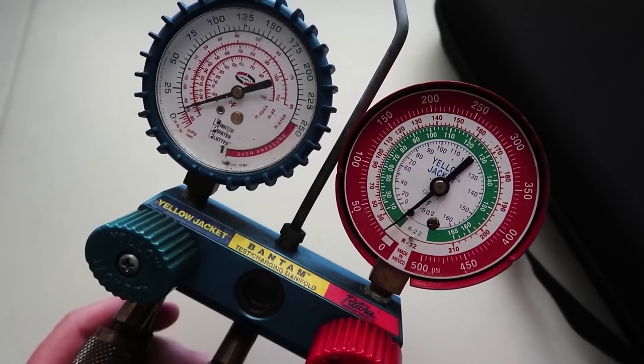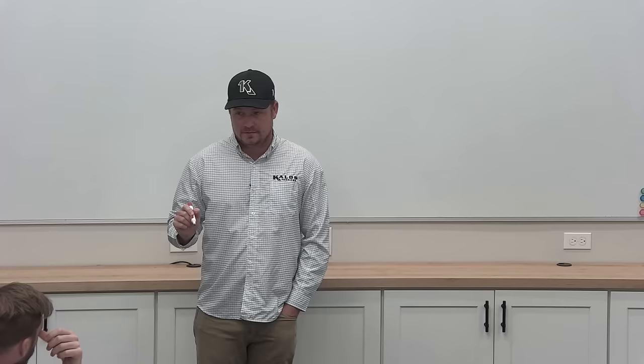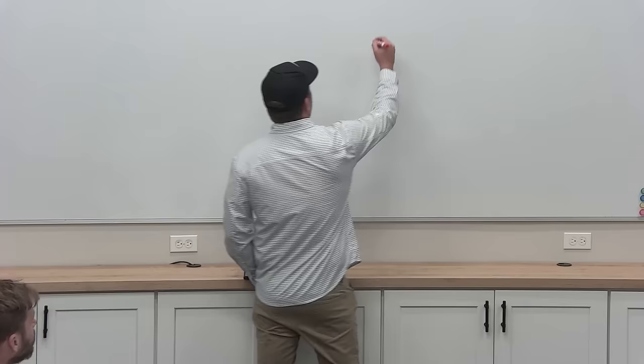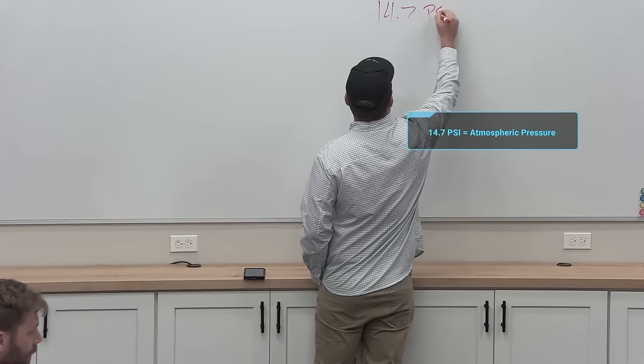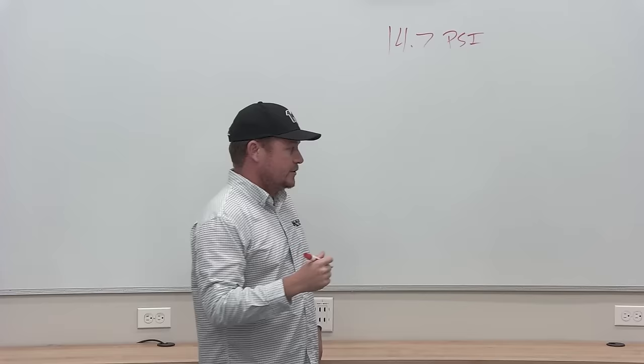So how do you take gauge pressure and convert it to absolute pressure? You add atmospheric pressure — 14.7. What does 14.7 represent? Atmospheric pressure. That is the pressure we see at sea level. We're sitting at the bottom of an ocean of air stacked on top of us — that's 14.7 PSI exerted.